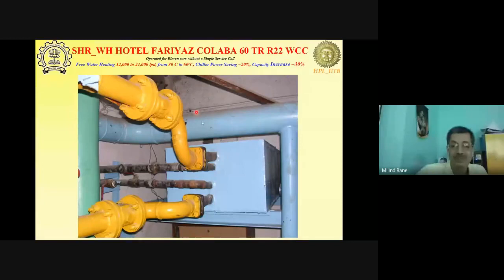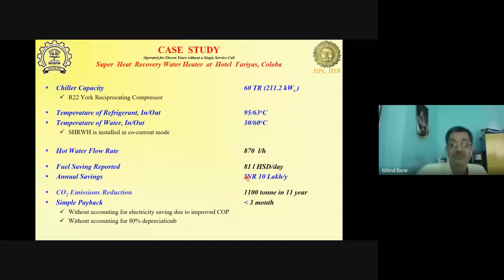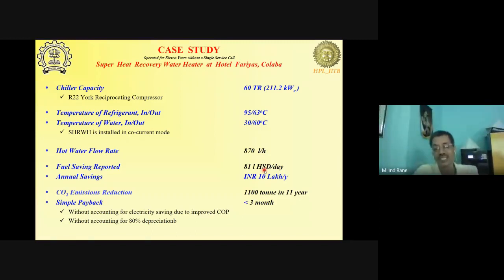This was a unit which was fabricated as part of my PhD student's thesis work. And here we had promised them a 6-month payback. They actually got a payback of 3 months, 2.86 months to be precise. And the CO2 emission saving was around 1,100 tons in 11 years. The annual saving was 10 lakh rupees, while the installed cost was only 2 lakh rupees. And the best part is after 11 years, when they scrapped the unit, they got 5 lakh rupees for the scrap value of the copper. Copper prices had gone up from 180 to almost 660 when they scrapped the unit.